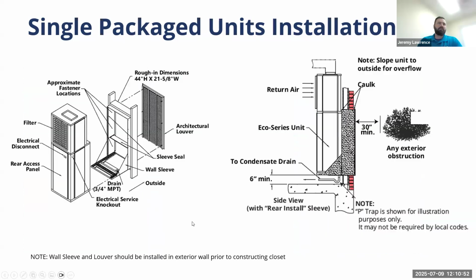How they fit together into the building. The structure of the building goes up and there's a pre-planned wall penetration. In this case, rough dimensions are 44 inches high by 21.5 wide for the sleeve to fit in. The sleeve comes with a cardboard block-off panel, so there's very little air exchange through the winter months. And then usually you put the sleeves in, and a couple of months later, you're ready for the units.